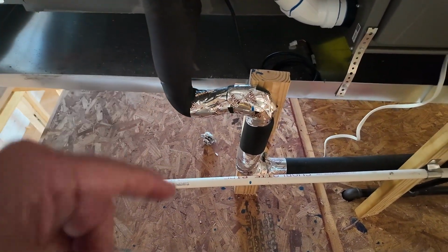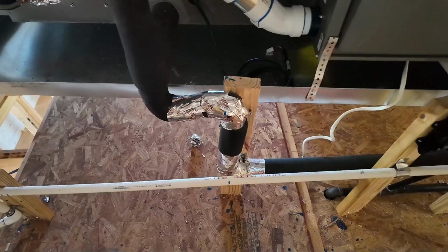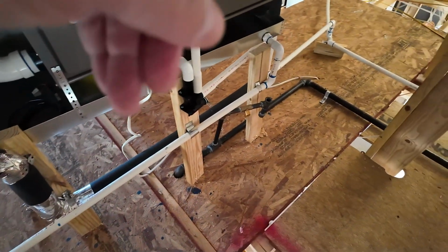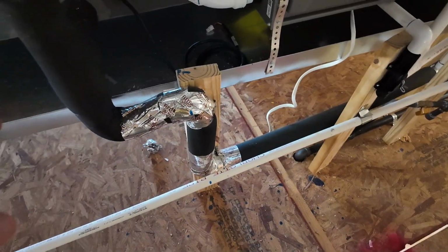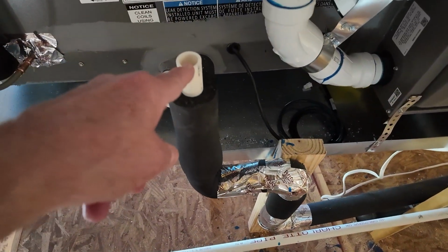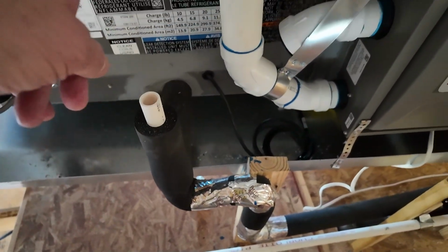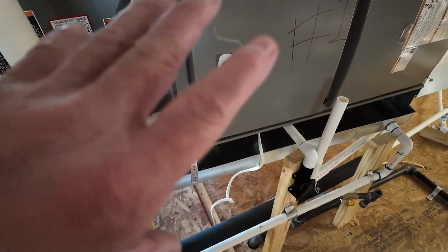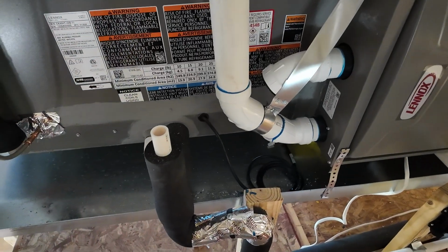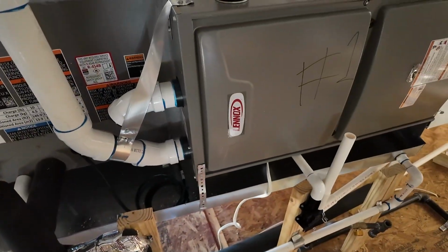And when that trap's empty, well, then there's nothing to keep the gases. What gases? This pipe goes to the sewer. So there's nothing that keeps the sewer gas from coming up, coming into your attic, and even more importantly, going into your indoor air handler. When the fan comes on, it starts blowing it all out. It gets evenly distributed throughout the structure.